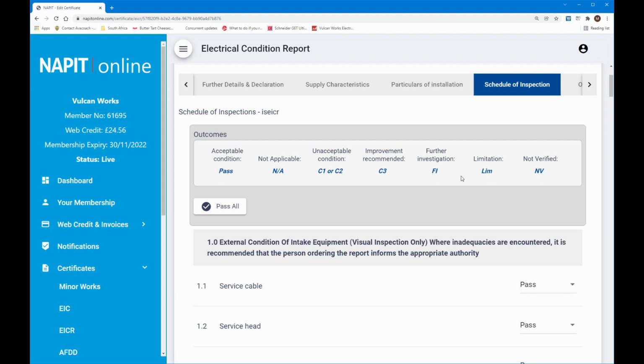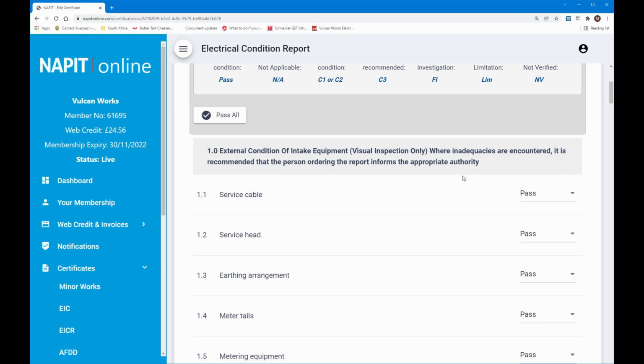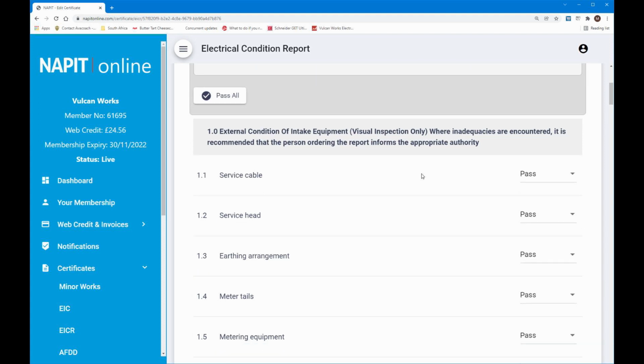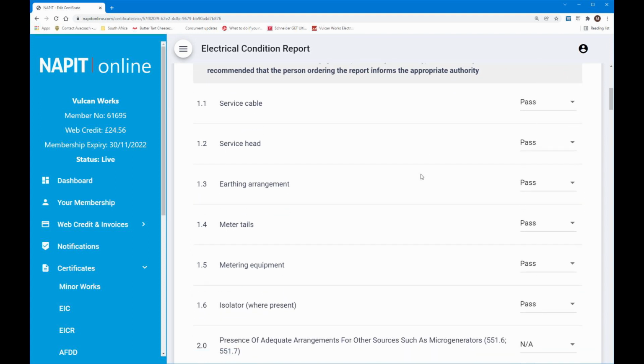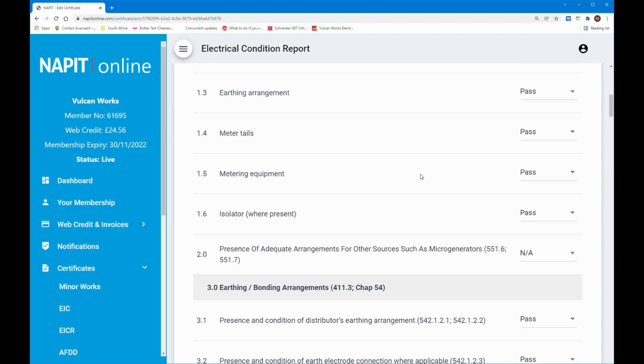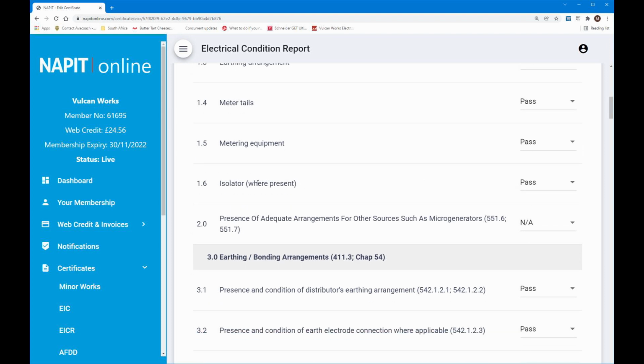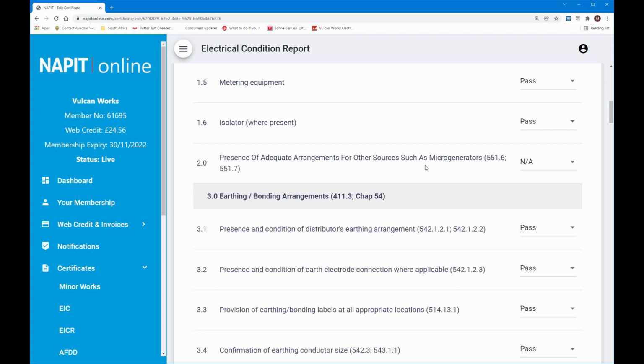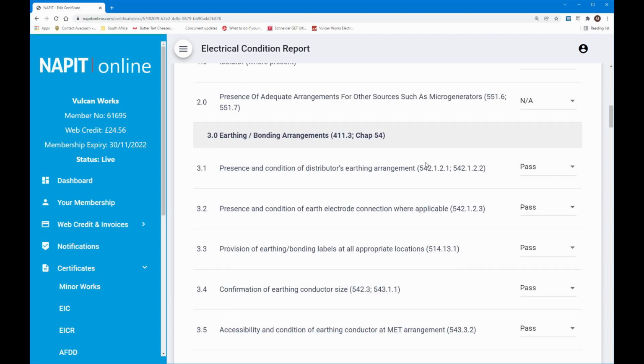Right, so let's run through this particular installation. I've actually gone through and filled these all in already, just to save a bit of time on the video. As you can see on this part, I've passed the service cable, the service head, the earthing arrangements, the meter tails, the metering equipment, and obviously now there's an isolator, so that's passed. It's not applicable for micro generators because there aren't any. So that's that bit. That was nice and easy.